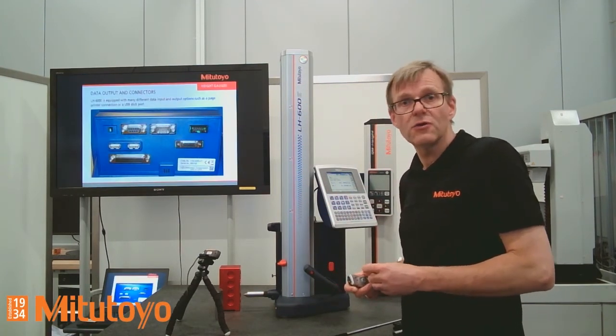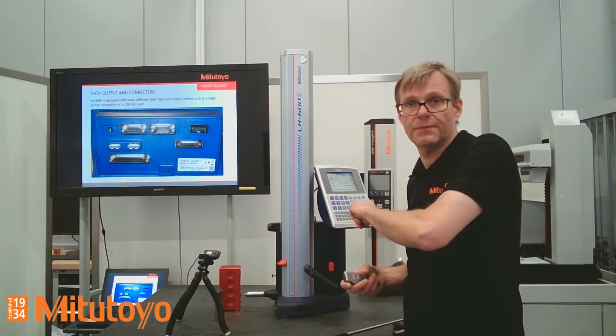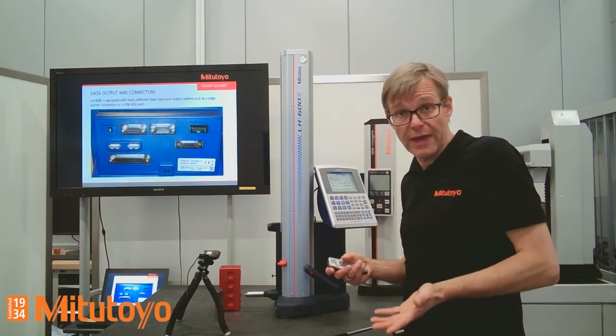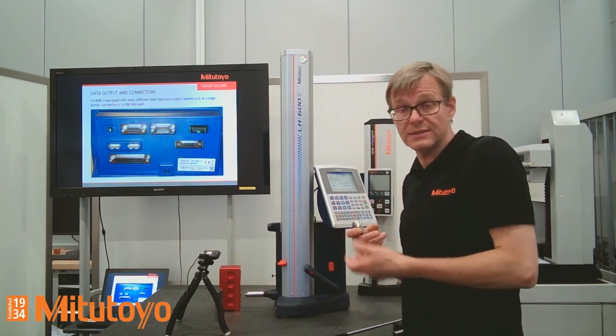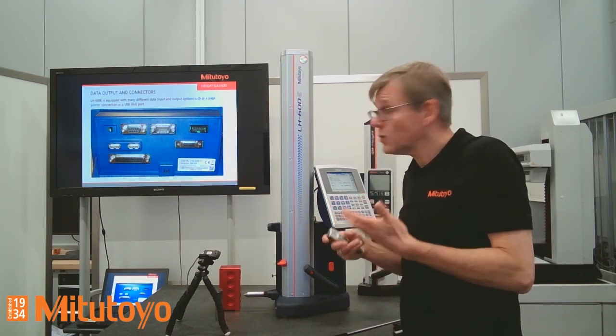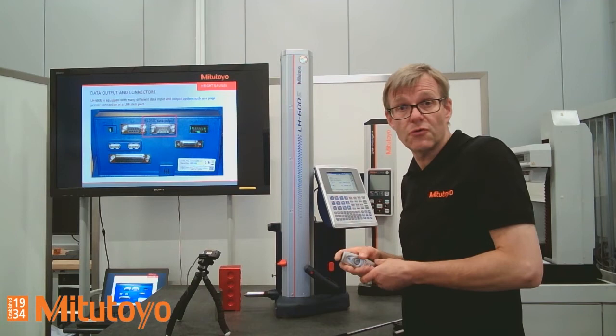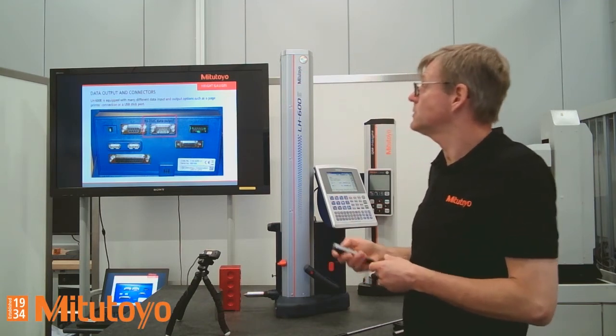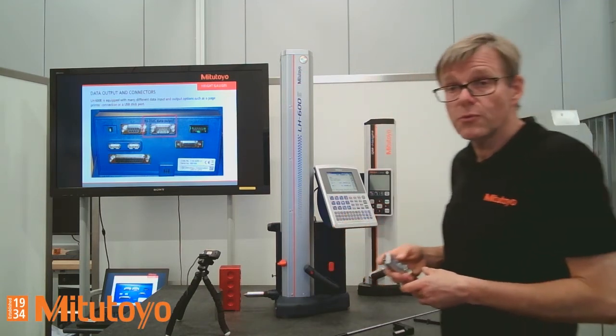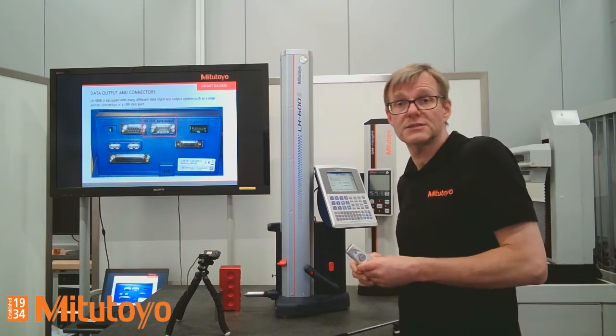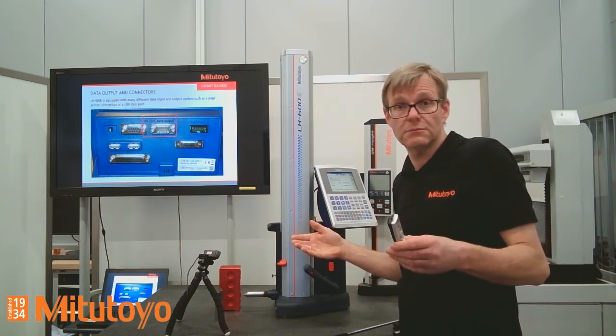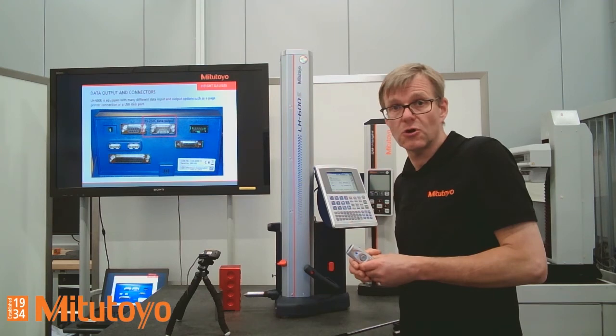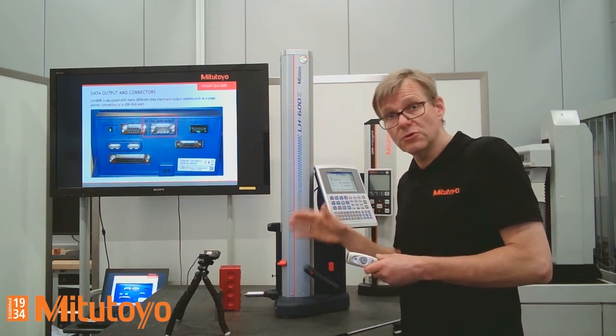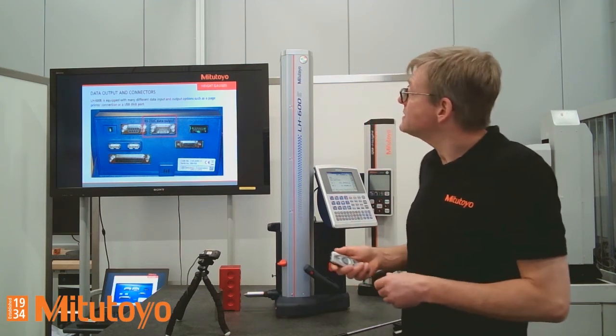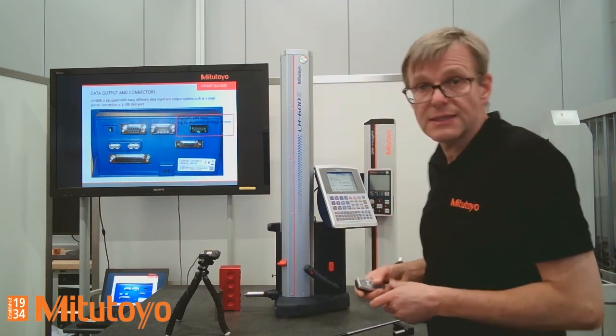So let's have a look at the backside of the instrument. So what kind of interface we have, what kind of, let's say, connections we have. So first of all, we have a serial output. So a serial output can be used to send the data directly to Excel or directly to any kind of professional SPC software. I will show you this later on. The second interface here is a digimatic interface.